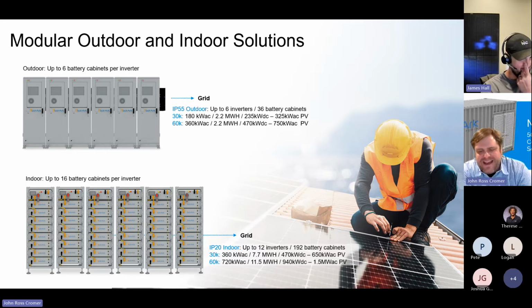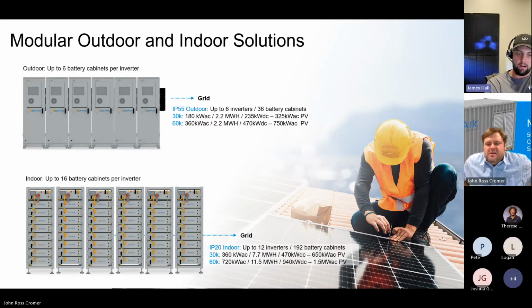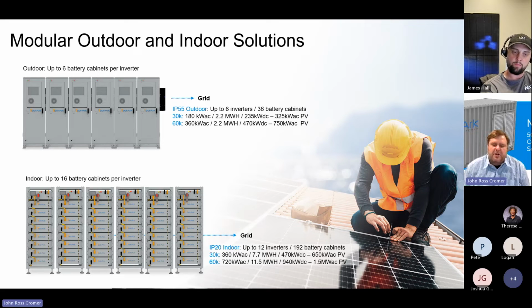Probably. But let's talk about battery connections to the inverters really quick. On the 60K and 30K, you have a 50 amp input on each battery input. How would you go about busing, let's just say, 3 batteries together on one input to the inverter? Yeah, so the battery cabinets come with an internal 150 amp bus bar. So it's very easy to parallel 3 battery cabinets to each other. And then the inverter has 2 battery ports. So it's very easy to parallel 6 outdoor battery cabinets to one inverter because of the hardware that's included in the outdoor cabinet. Now, the indoor cabinet is a cheaper cabinet, a cheaper system. It's designed to be in an authorized personnel battery room.